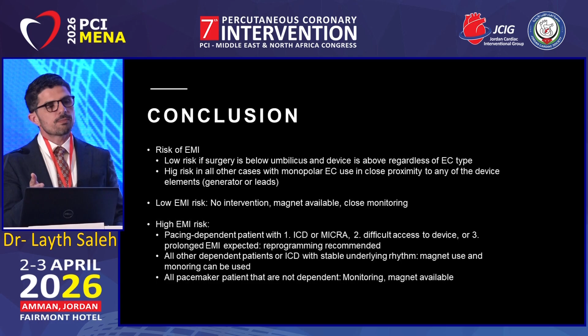On a pacemaker, most pacemakers, the exception is the one that I mentioned, which is the Micra leadless pacemaker. Most pacemakers with a magnet will go to an asynchronous mode where there is continuous pacing, no sensing, so that even if there is EMI, there is a stable rhythm during the case. And then the last note I want to mention is that dependency is not just a rhythm, it's a clinical diagnosis. So we need to know that there is a rhythm and that it's a perfusing rhythm. So 35 beats per minute may be enough for many people, but for some people it should be 60 or 70. And with that, I think I will finish.